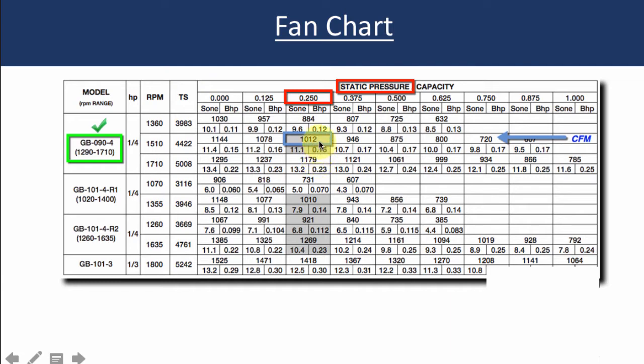Now the way they get more CFM using the same model, this model will do 884 up to 1179. How they do that is changing the speed of the fan, revolutions per minute, RPM. So at the smaller CFM it's going slower. They speed the RPMs up, speed up the fan, they get more CFM at the same static pressure.